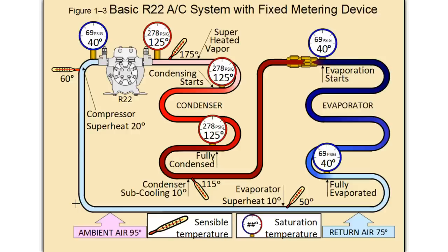As we leave the compressor, we have 278 psig superheated, high pressure, high temperature gas — 100% vapor. Our thermometer shows 175 degrees line set temperature. That doesn't correspond to what our gauge says at 125 degrees, because this is superheated vapor — it is not in the saturated state. So it's normal to see a difference between what your gauges tell you the pressure is and what a thermometer would tell you at the outlet of the compressor.